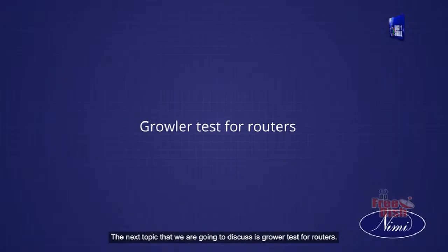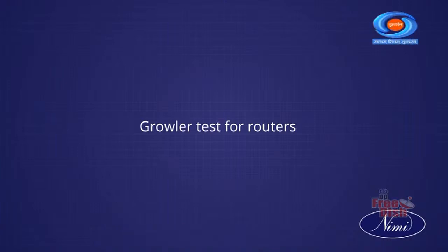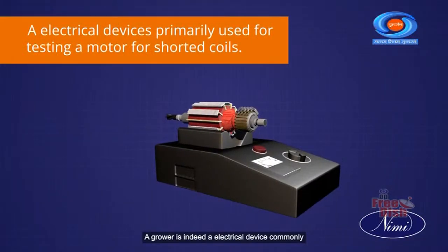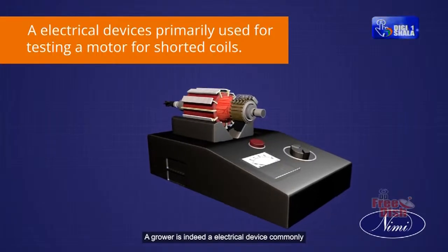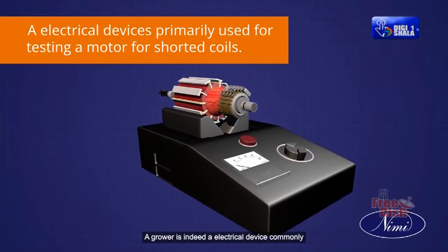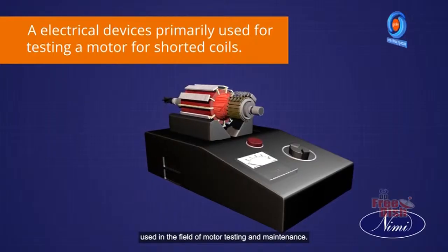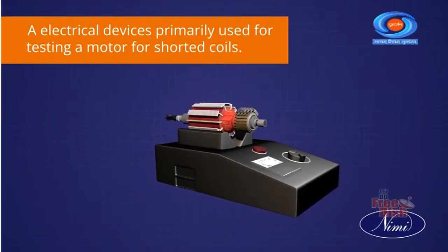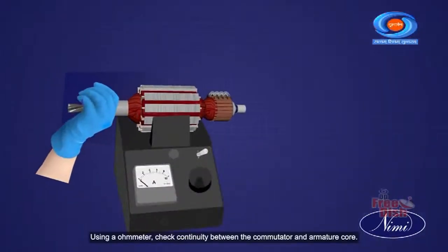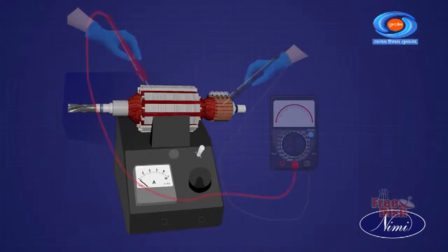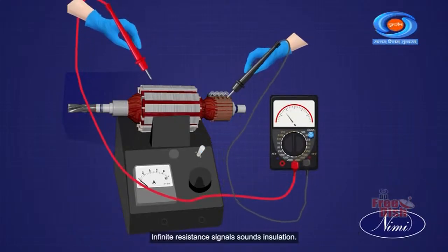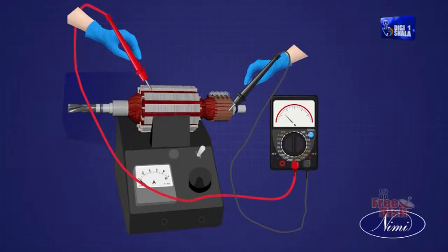The next topic that we are going to discuss is the growler test for armatures. A growler is an electrical device commonly used in the field of motor testing and maintenance. Using an ohmmeter, check continuity between the commutator and armature core. Infinite resistance signals sound insulation.